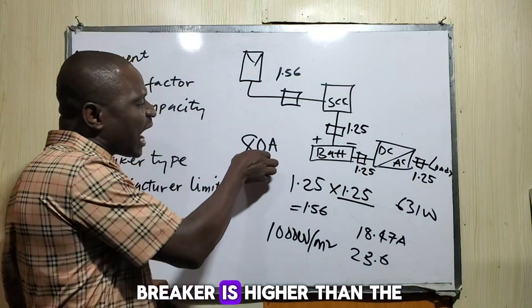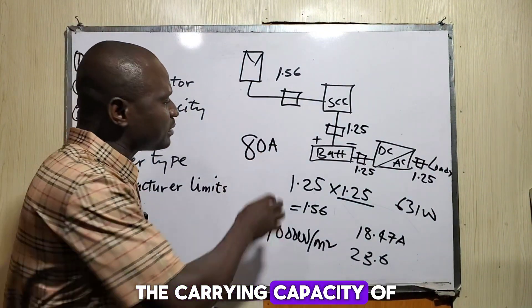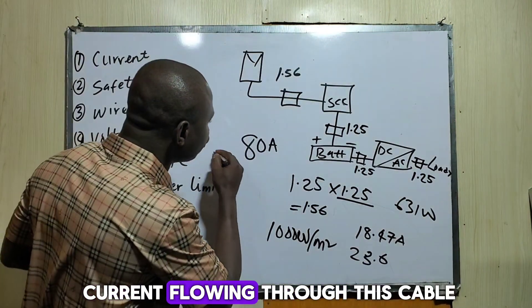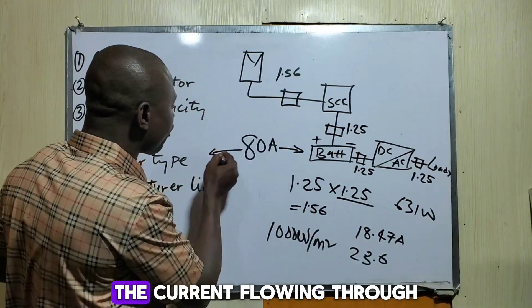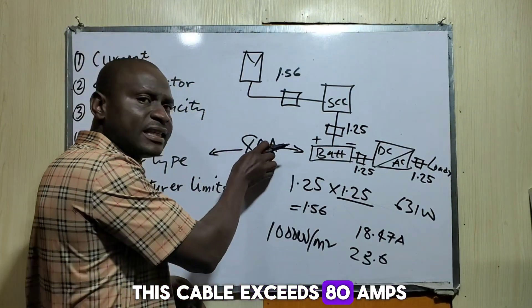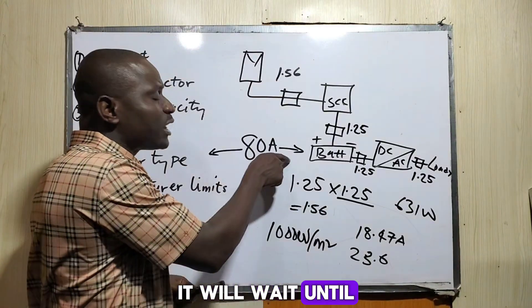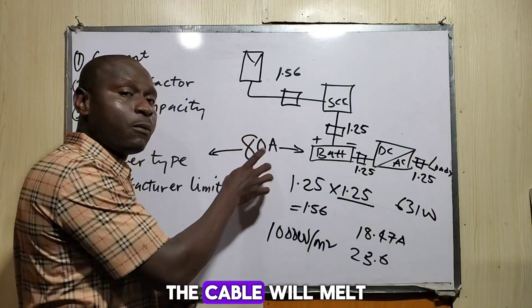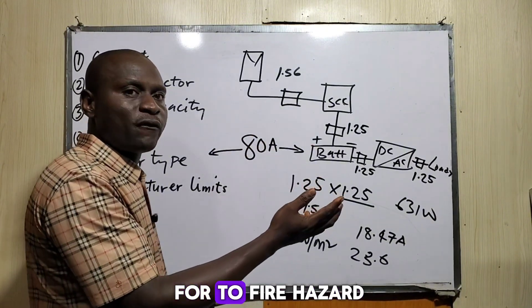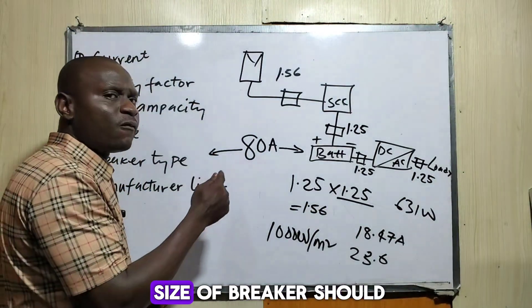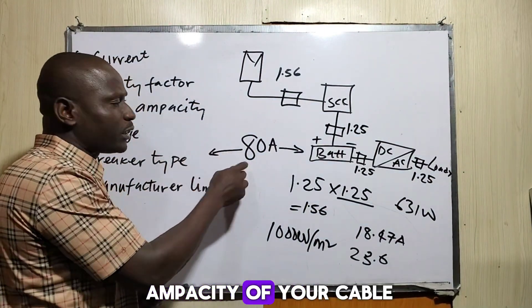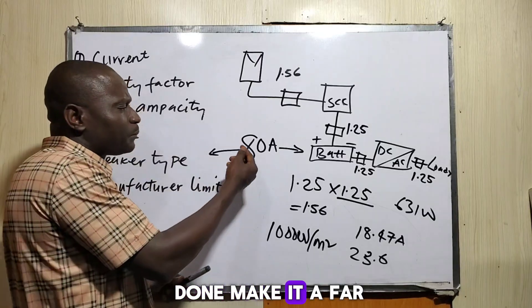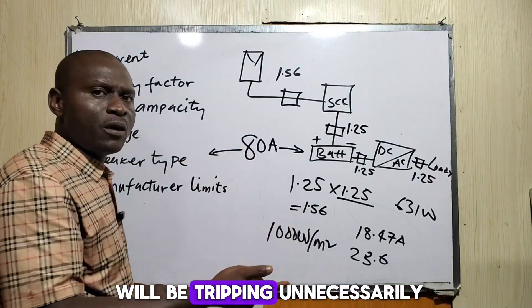The breaker size should not be 100 amps or 125 amps if the cable is rated 80 amps. The main purpose of a breaker is to protect your cable from overheating or melting due to high current. If the breaker rating is higher than the cable's ampacity — say 100 amps — the cable will already be overheating before the breaker trips, which can lead to fire hazards. However, don't make the breaker far too small either, as it will trip unnecessarily.